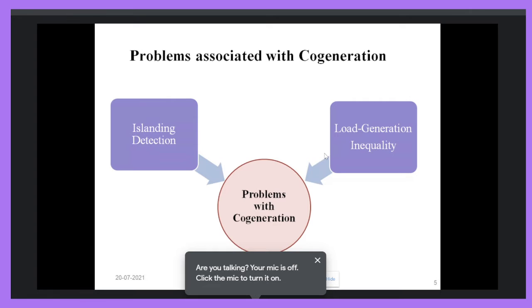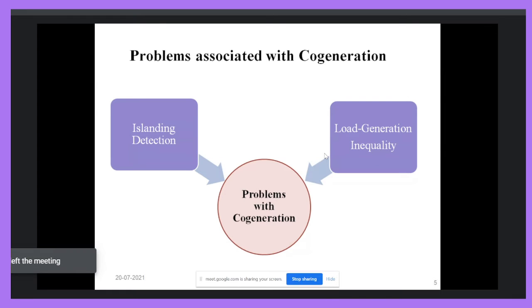How can we detect islanding? Nobody can say what type of fault has occurred in the grid without observing the parameters of the grid, because the utility grid is a very huge network, with a number of generators and many loads connected. So we have to detect the condition for which we have to separate the industrial system from the utility grid. That is called islanding detection. We can detect islanding on the basis of observing different parameters like voltage, frequency, power flow direction, and rate of change of frequency.